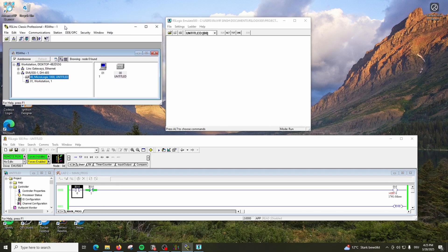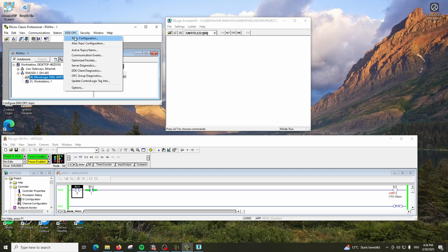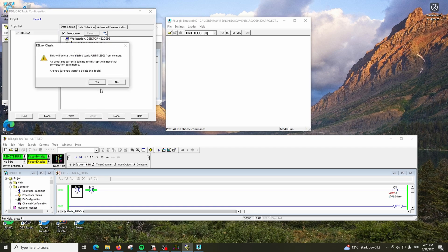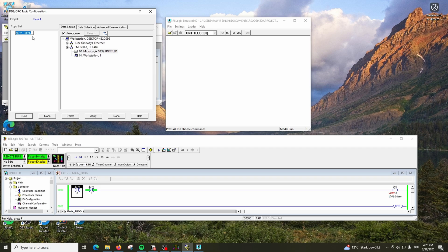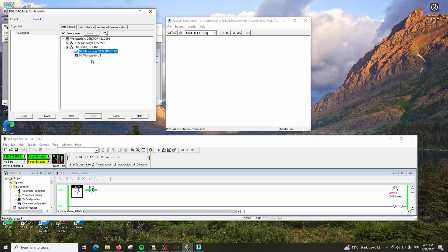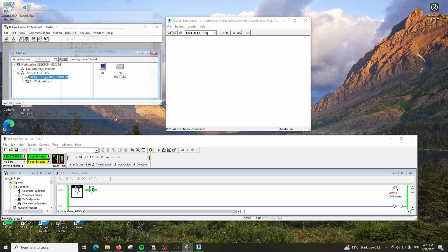Before coming to Ignition SCADA, we have to do one more step. We have to link a topic to OPC DA. Go to DDE OPC Topic Configuration. I'll create a new topic - let's call it RSLogix 500. Once you create that, select the controller which is the emulation one. Click Apply. This will update the topic and now these two are connected. Click Done.